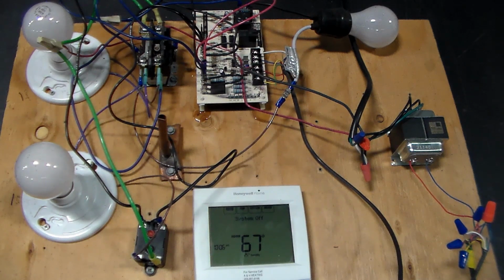This board doesn't have that option. It doesn't have the outdoor sensor. But some of the newer heat pumps do have the outdoor sensor, where they'll literally, when it gets too cold outside, just stop running the heat pump part and send that W signal back indoors. So the W on the board has two functions. One, to turn on the backup heat during defrost, so we're not blowing cold air, quote unquote, onto the customer while we're essentially running cooling during defrost. And the other function on the newer boards of that W is, if it gets too cold outside, the heat pump will lock itself out. It'll send that W back in and run your backup heat, because that would become more efficient than your heat pump once your heat pump drops below its COP.